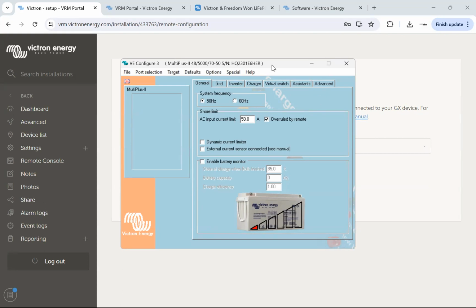So what we need to do is make these changes and then upload the file to the inverter. It's a bit different from when we were programming the remote console, the GX device, the Cerbo GX or Color Control GX or whatever GX you've got. There, you could use the remote console to program it, and any change you made would be live online. This is offline programming—we've downloaded the file, opened it in the VE Configure app, and we're going to make changes, then upload it.